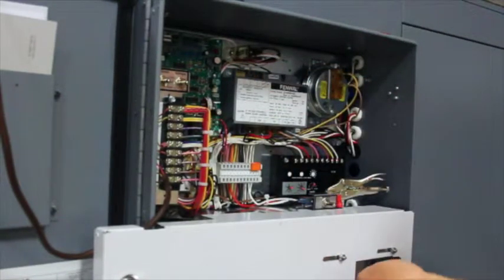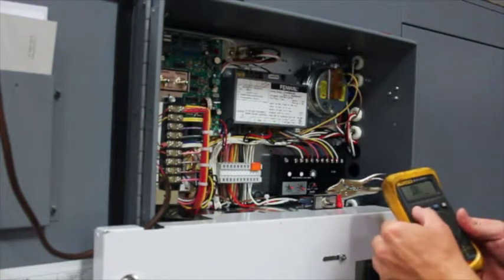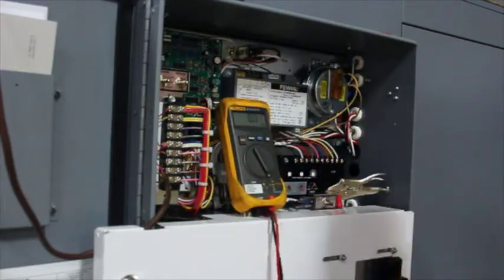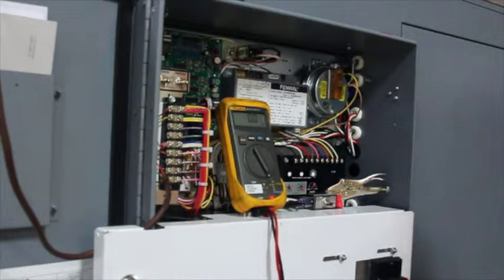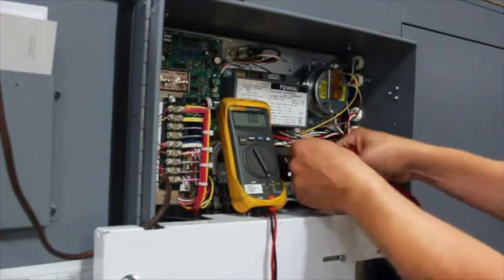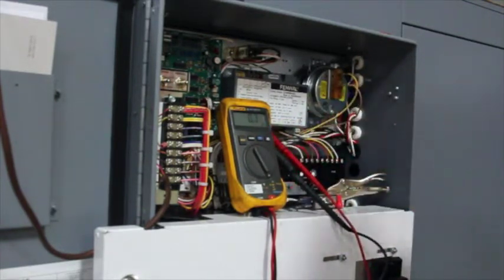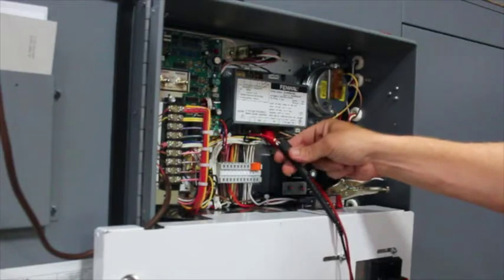Once the new board is installed, it is important to verify the operation of the board to confirm it is functioning properly. You will need a DC micro-amp meter set to DC micro-amps. Remove the red wire off the Fenwal board and place your meter in series at that point by removing the wire, placing the black alligator clip on the push-on connector of the wire you removed, and taking the red alligator clip and placing it on the spade of the board marked FP. Make sure that it is secure and it is on FP.